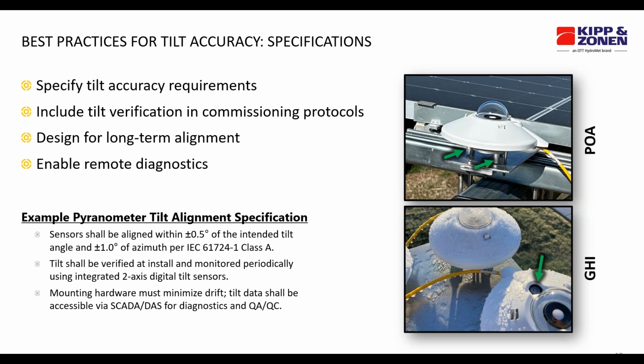Additionally to the sensor itself, you should think about the environment around the sensor. So you might want to specify mounting hardware that minimizes drift or settling as you consider the environment the pyranometer is in. And for example, specifying that the MET station has a buried section rather than a pad-mounted attachment style on something like a 4-inch pad that might be susceptible to frost heave or runoff related settling.